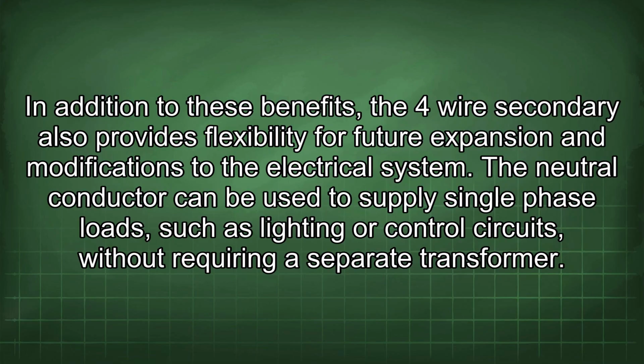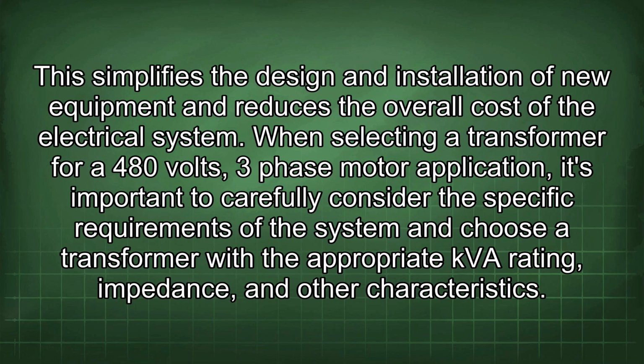In addition to these benefits, the 4-wire secondary also provides flexibility for future expansion and modifications to the electrical system. The neutral conductor can be used to supply single-phase loads such as lighting or control circuits without requiring a separate transformer. This simplifies the design and installation of new equipment and reduces the overall cost of the electrical system.